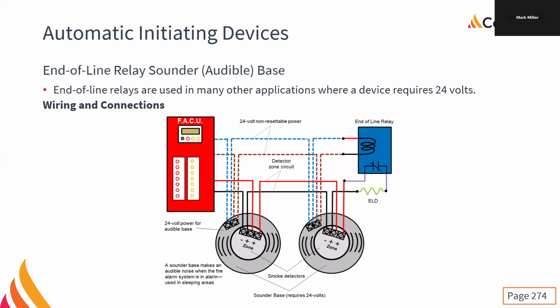Not shown on here is the interconnection wire, right? Here we see two separate sounder bases. The only time these bases make noise is when that smoke detector goes into alarm. It does not make an audible noise when any fire alarm zone activates. If you pull a pull station 3 floors down, nothing's going to happen to these sounder bases. It's only in the immediate area, just like a smoke alarm. But there is a third wire you can add, the interconnection wire, just like we do on smoke alarms. So if we have multiple of these devices in an apartment, we can interconnect them just like we do with smoke alarms. And so all the sounder bases in that apartment will activate if one of them goes into alarm. So we can interconnect all this stuff.